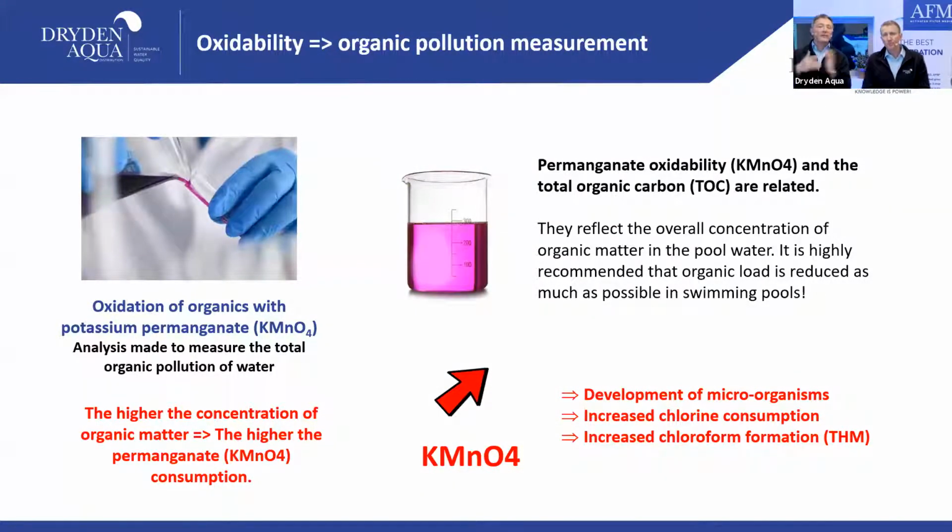Yeah, absolutely. TOC and KMnO4 are related, just a different kind of measurement. If you measure TOC and multiply it by 1.5, you get to KMnO4. So it's just a different measurement, but it's about the same. It's the oxidability, how much KMnO4 you have to add to the water until everything is oxidized. The higher this number is, the more organics you have in the water.